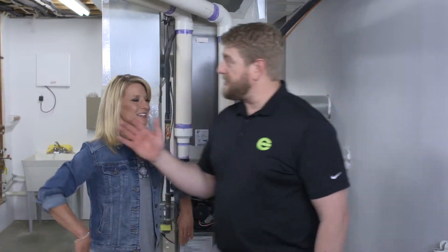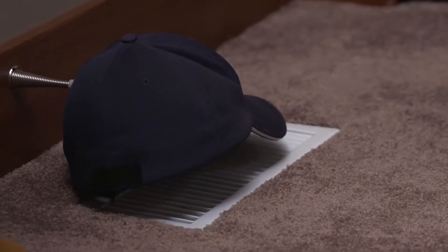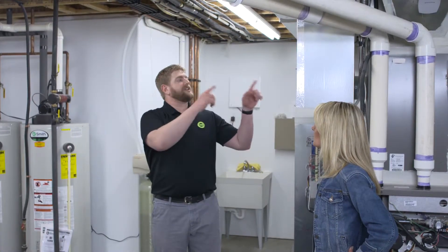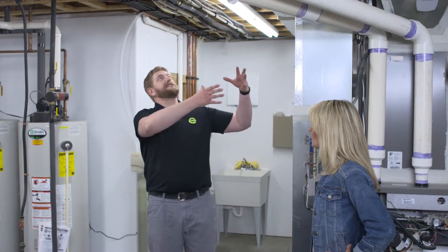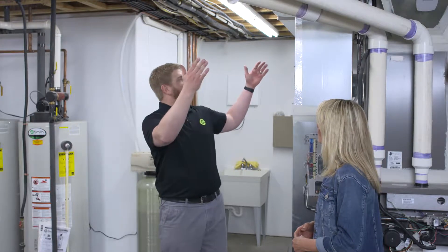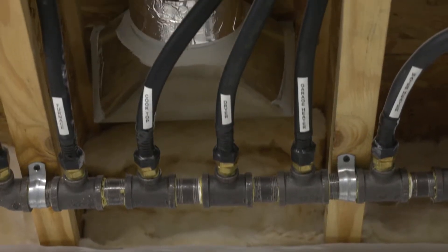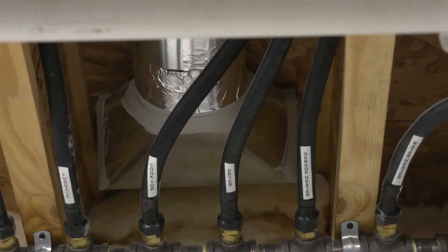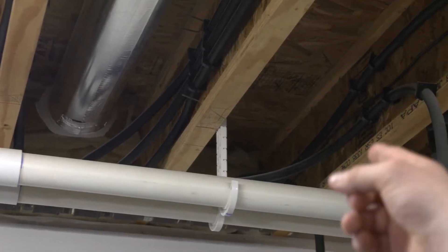The original reason we got called was for the room with really high airflow and loud noise. What we found was the duct that went to that room actually connects right over the furnace, and when that happens, the airflow from the blower has no resistance — so you get way too much air and a lot of noise. Like a proximity issue. And where that duct connects is not controllable by the zone dampers, so regardless of whether the basement or main floor thermostat is calling for heat, that room is always getting heat blown into it.